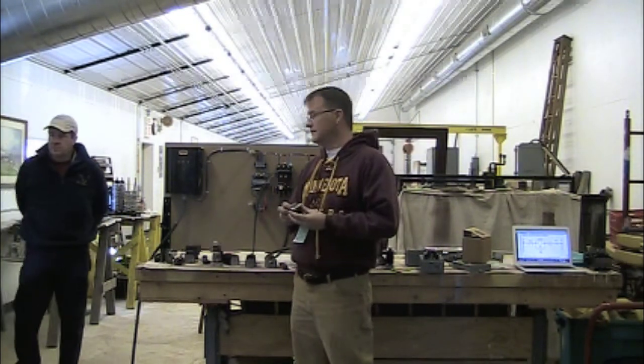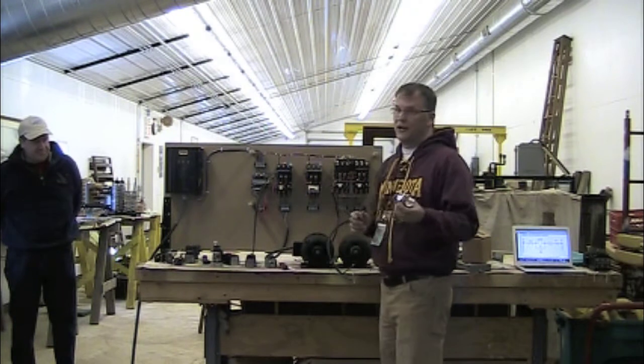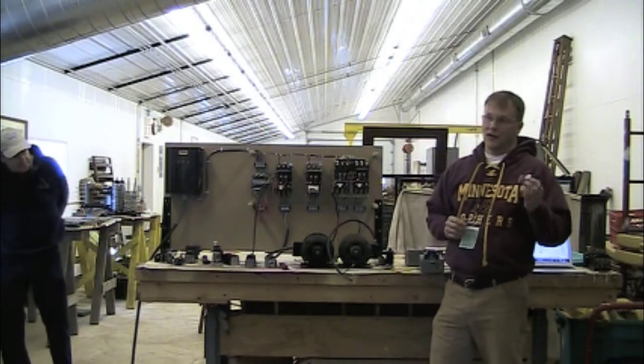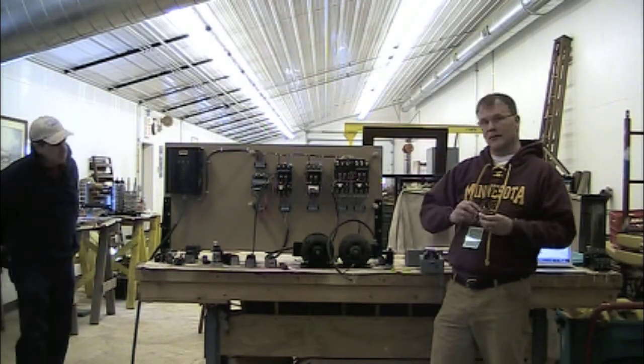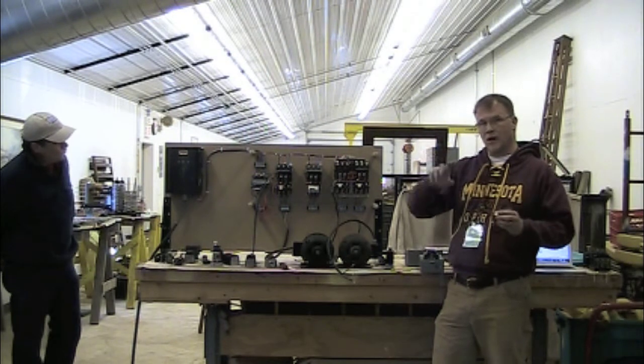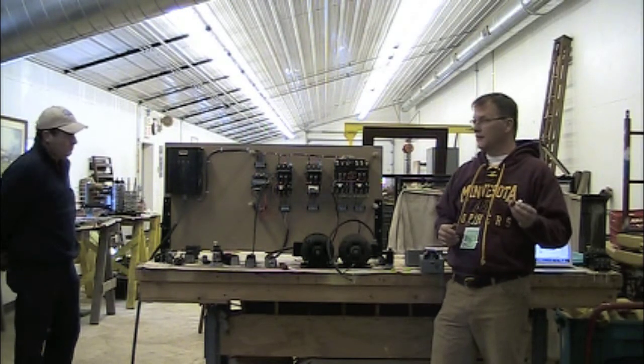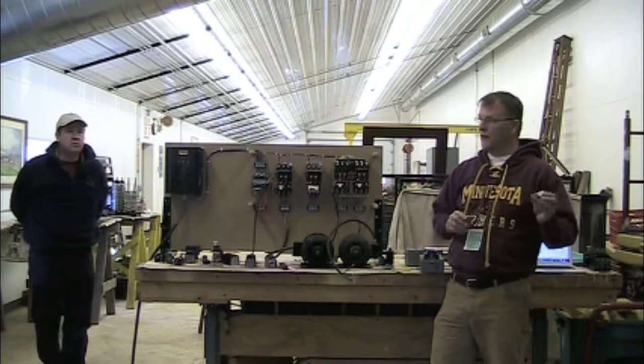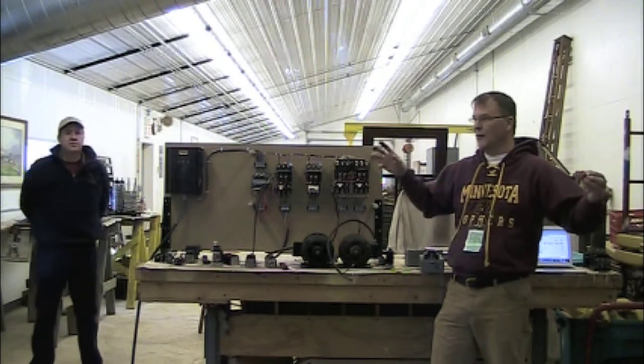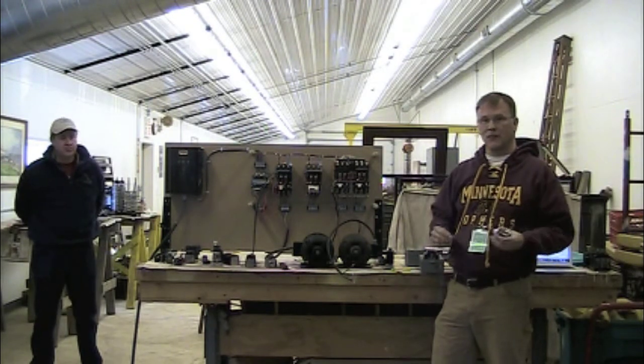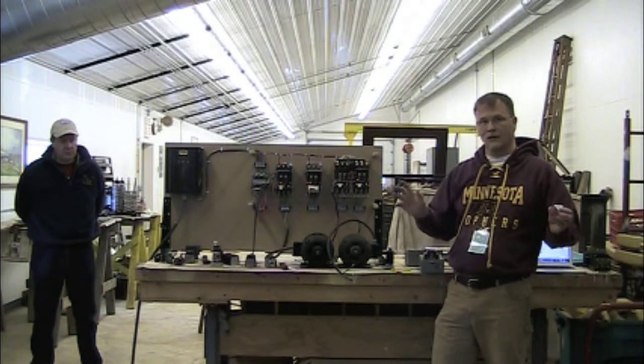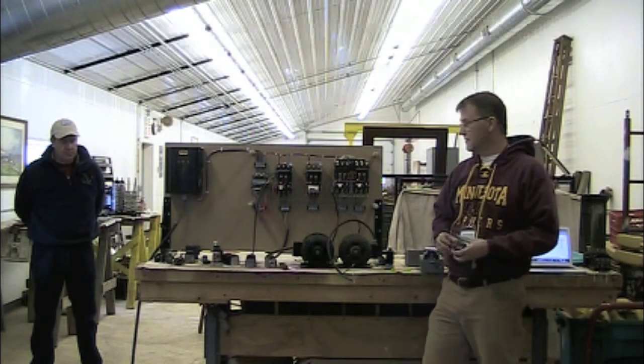So these are also nice. If you're controlling multiple motors or something, you can have this upstream of multiple contactors so that nothing's going to run until you pull this as the reset. You arm the whole thing, and then you can control the other motors, and then one stop can control all of the motors on the device.